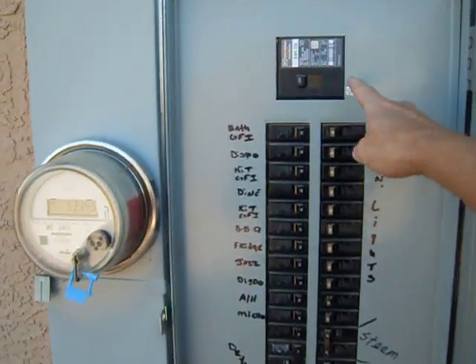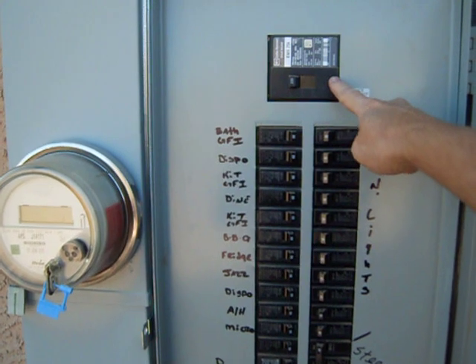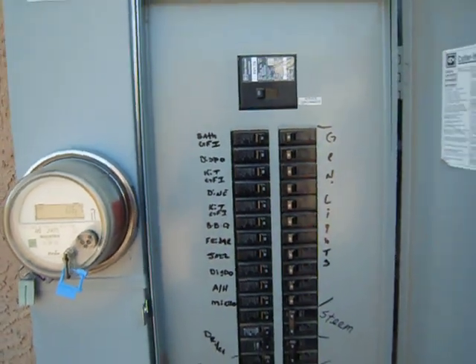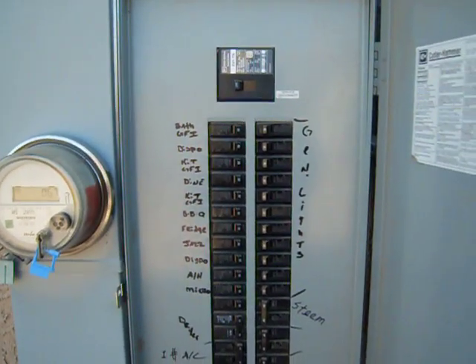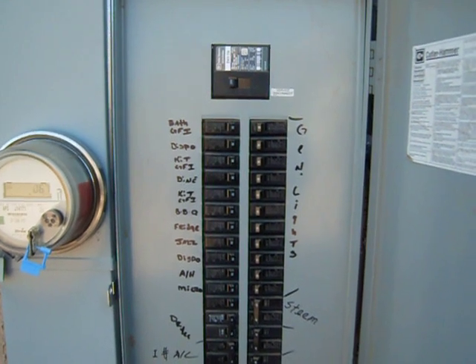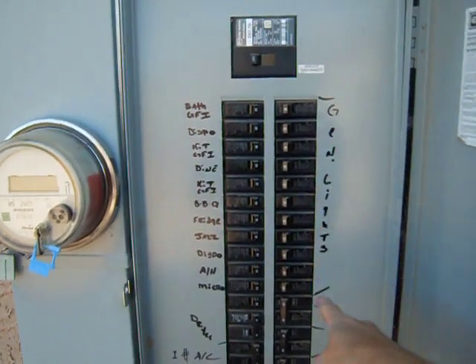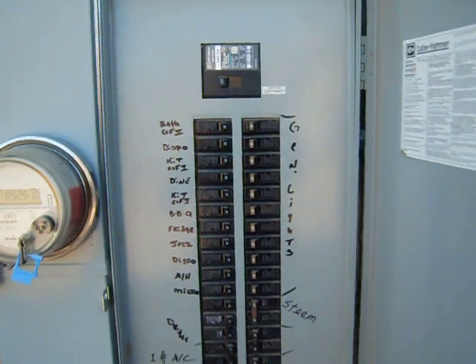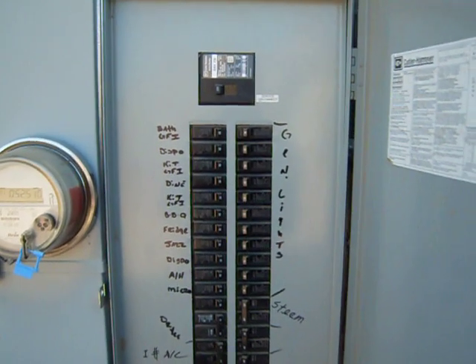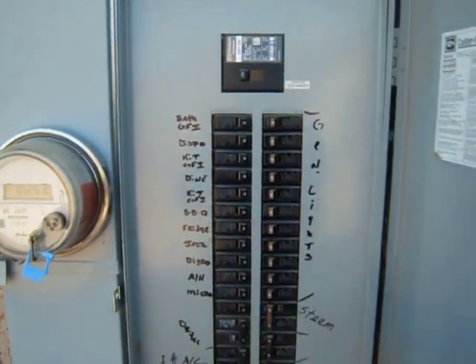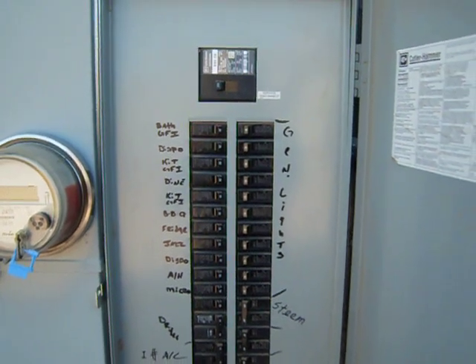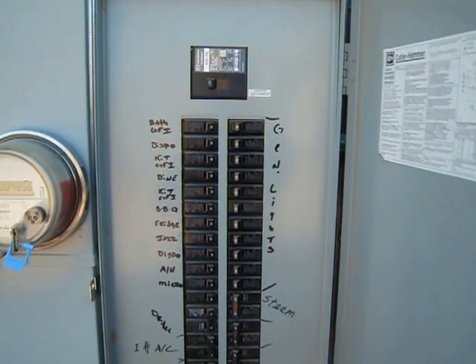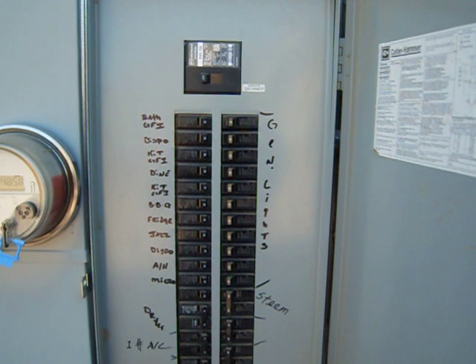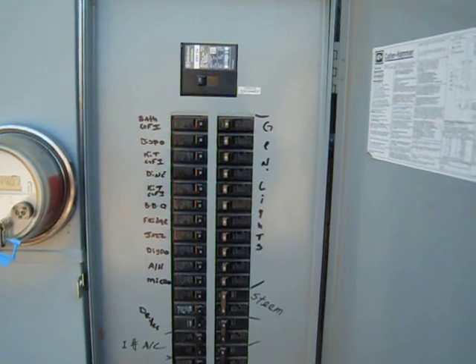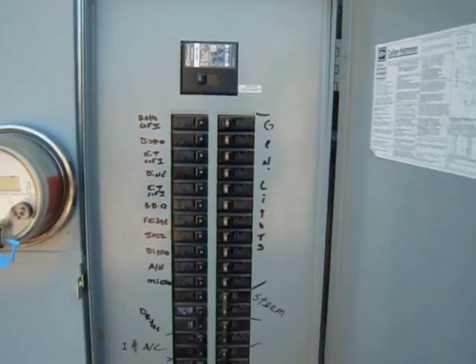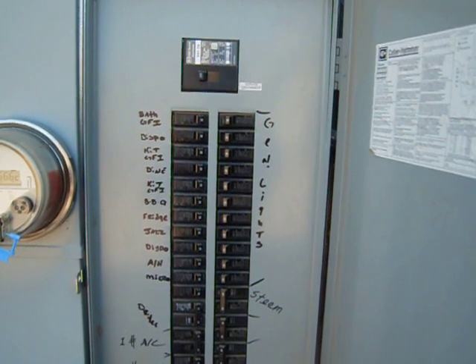One of the first things you're going to want to locate in your panel is your main shutoff breaker. In my case, I've got a 200 amp panel, and what that breaker does, when you open it, it'll kill power to the rest of the panel, and that's for doing maintenance. You have other individual circuit breakers. You'll have single pole breakers, which are the single circuit breakers, and you'll have double pole breakers, which are two breakers connected together. Your single pole breakers are all 120 volts, and your double pole are 240.